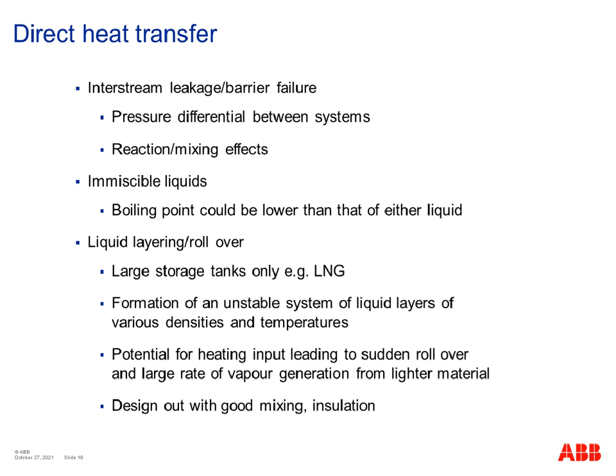It gets less and less dense as it gets warmer. So you've got this buoyancy effect where it kind of wants to move above the denser layer above it, but it can't because of the static head of that layer of liquid in the tank. But if that situation carries on and the density difference continues to increase, then you may suddenly get a situation where it can overcome that static head of the fluid above it, and this is called rollover. So it will suddenly push that material out of the way and move to the top of the tank, and then that will start to vaporize very, very quickly. So you can get an enormously high generation rate of vapor in this rollover situation. So it can be quite dramatic and lead to very high relief flows.